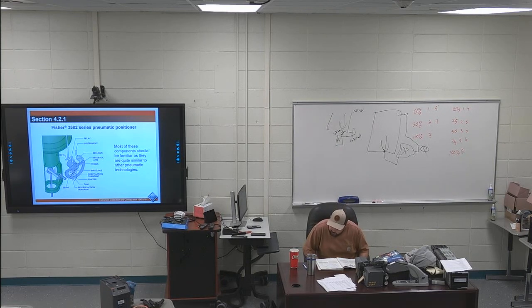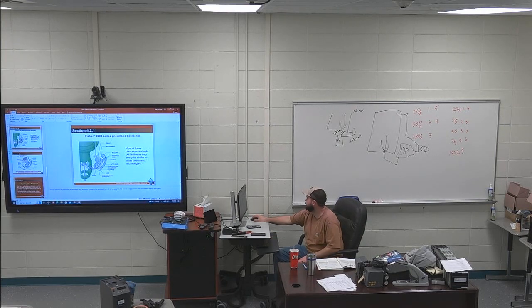Last sentence on page 29 is highlighted. Calibration can be performed in the field using the HART handheld communicator, or may be performed from a control room if the system is integrated with DCS technology. Distributed control system technology. That is all of my highlights. Let me stop the recording.